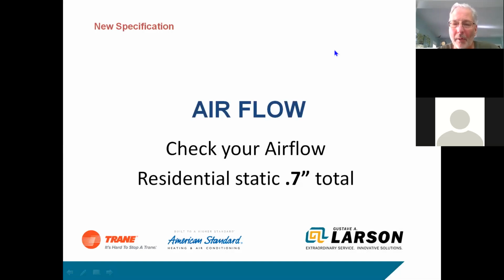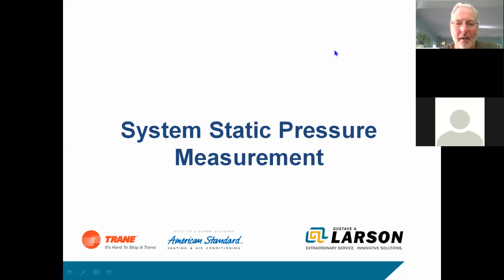One of the things that I want to point out on the Trane American Standard equipment is when we went to these new motors, the redesigned furnaces, we took into account that 0.7 is really the new norm. And if you're doing static pressure tests, it's impossible to get to 0.5 static anymore. I mean, by the time you put a coil in there and a high efficiency filter, you're going to burn up that 0.5 pretty quick. So in all reality, if you're at a 0.7 or a 0.8 static, you're probably in the realm of where you should be on a system.